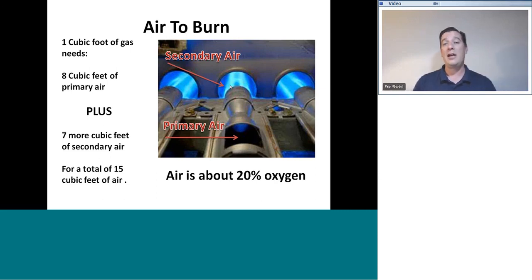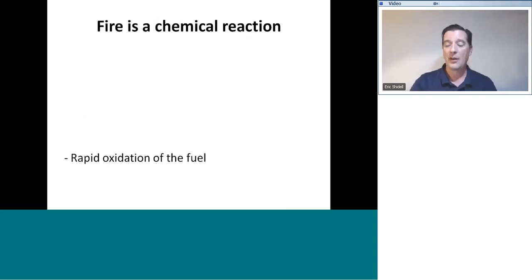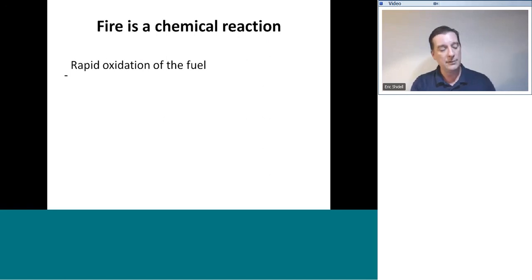That's a heck of a lot of air, and that air has to come from somewhere. And that is why the fuel gas code and also the mechanical code has such a strict requirement on combustion air supply. It's very, very important. If we don't have the right combustion air supply, our flames or gas burners aren't going to perform correctly. Here's a really cool thing to get deep in your head about combustion. Fire is a chemical reaction.